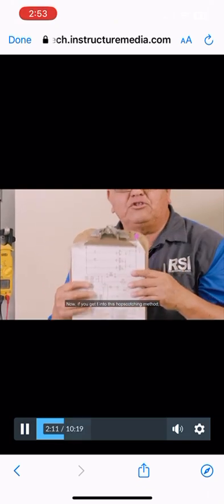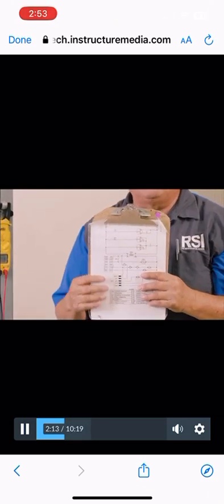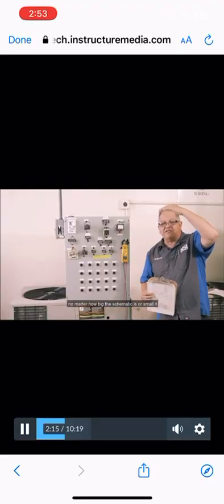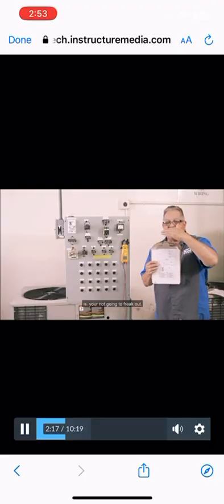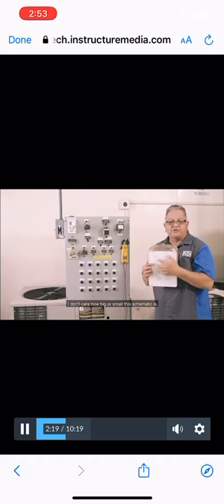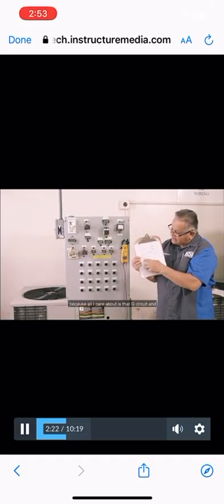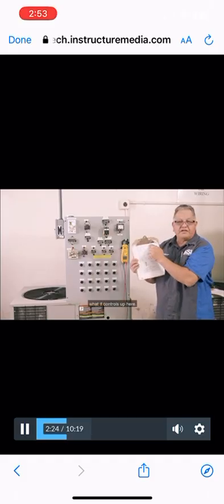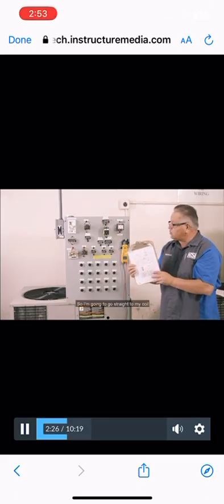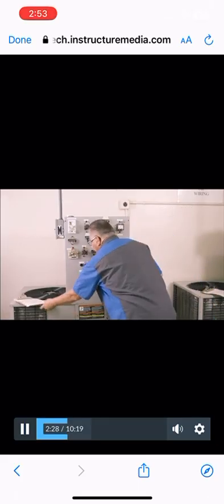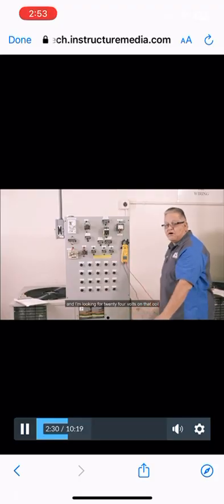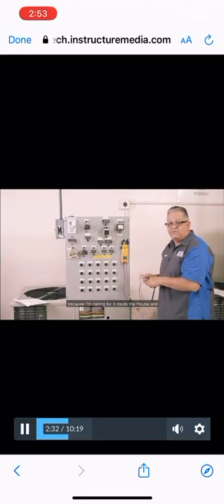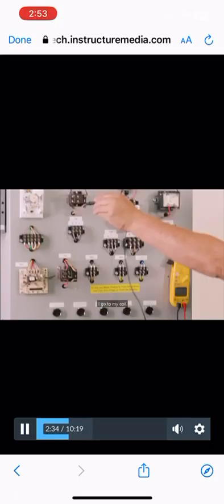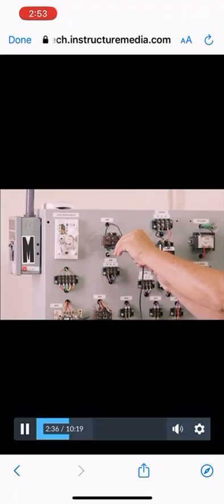Now, if you get into this hopscotching method, no matter how big or small the schematic is, you ain't going to freak out, because all I care about is that G circuit and what it controls up here. So I'm going to go straight to my coil, and I'm looking for 24 volts on that coil because I'm calling for it inside the house. And I go to my coil and I'm reading 0 volts.